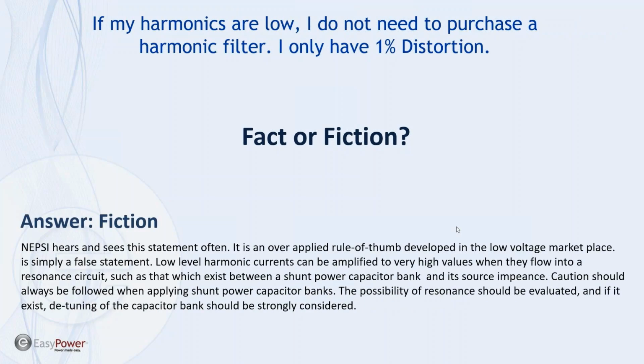So on to the next myth. I see this often: if my harmonics are low, I do not need to purchase a harmonic filter, I only have 1% distortion. Fact or fiction? The answer is fiction. We hear this all the time. It is an over-applied rule of thumb developed in a low voltage marketplace. It's simply a false statement.